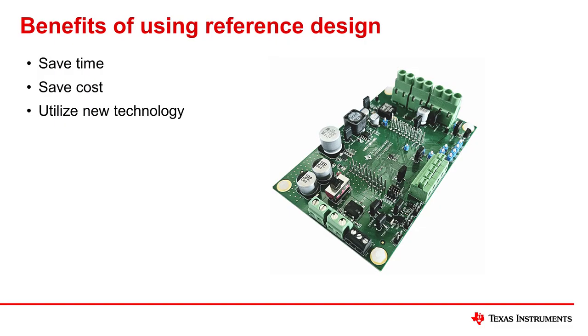By referencing this design during your own design process, there are several benefits, including saving time and cost. It's a low-power system which utilizes some of our newest TI devices and targets upcoming trends in the HVAC space. For example, our magnetic position sensing technology is able to accurately detect motor position immediately without the need for calibration or an extended turn-on period of the motor.